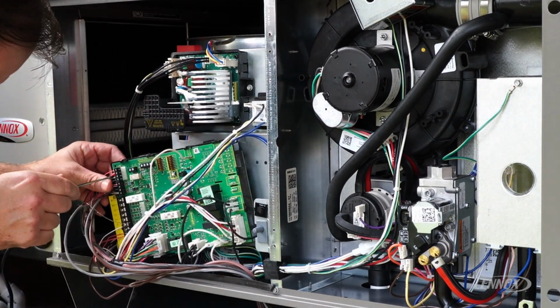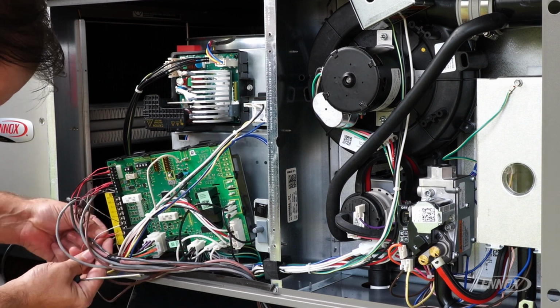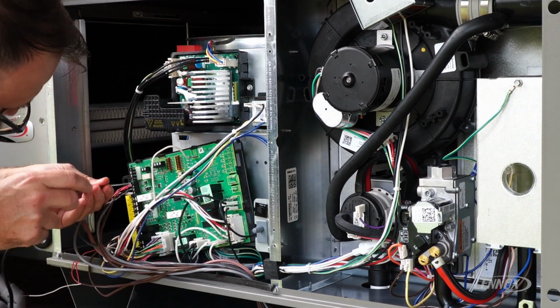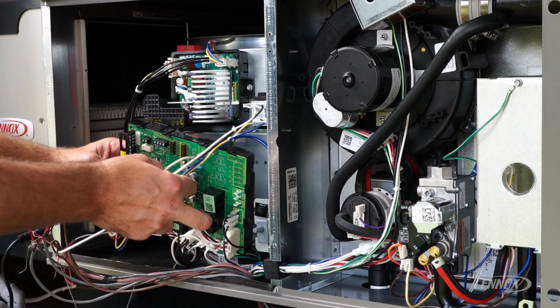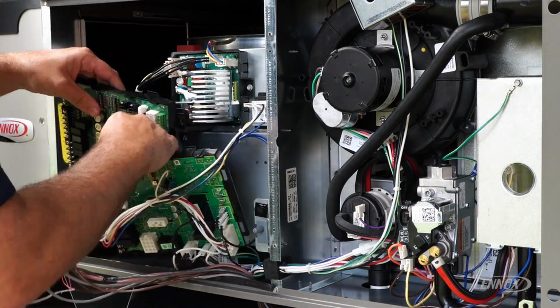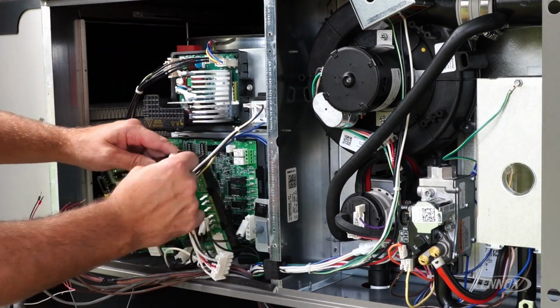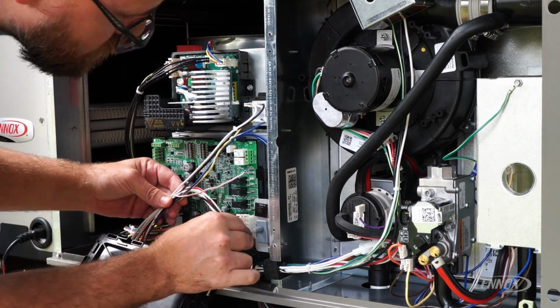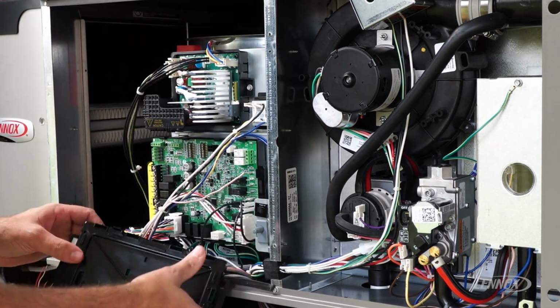A best practice I like to do when changing control boards is not to remove all the wires. I like to remove the bare minimum, just enough to get the new board in place, and then start transferring over the bulk of wires to the control, just 4 or 5 at a time. Don't get carried away, and always follow the wiring diagram.